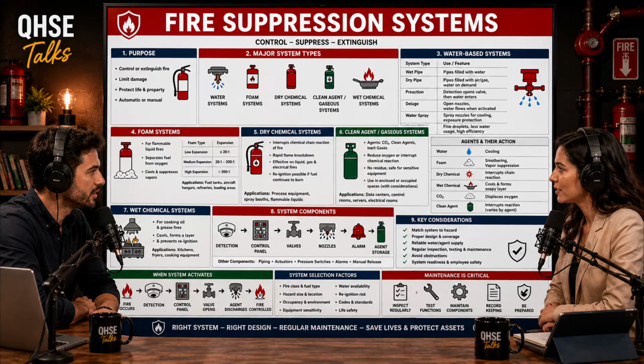Right, so a dry pipe system is specifically designed for freezing temperatures. The vast network of overhead pipes isn't filled with water. It's filled with pressurized air or nitrogen. So what holds the municipal water back? Down in a heated, insulated riser room, there's a specialized device called a dry pipe clapper valve. Below the valve is the pressurized municipal water. Above the valve is the pressurized air in the pipes.